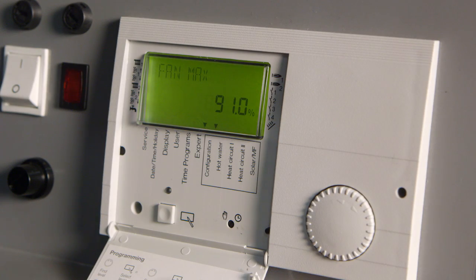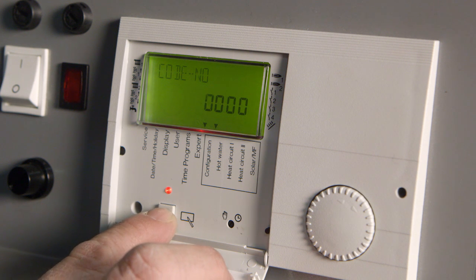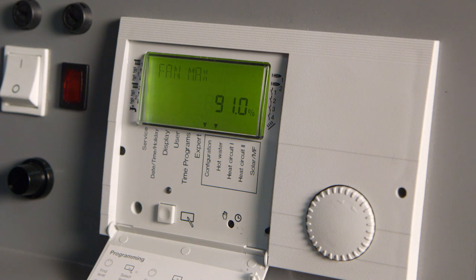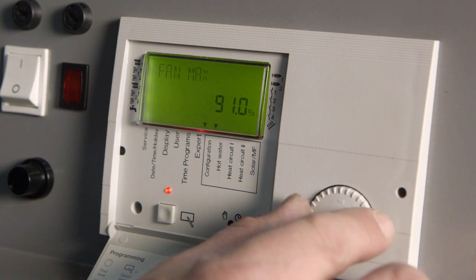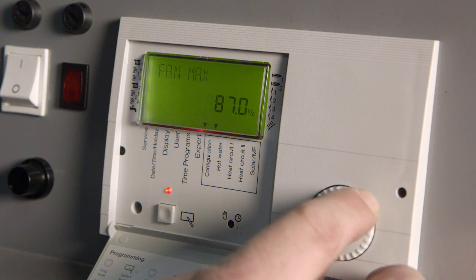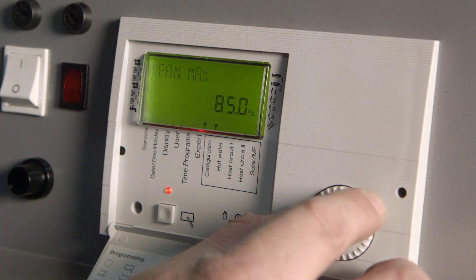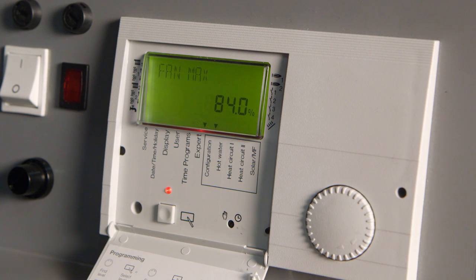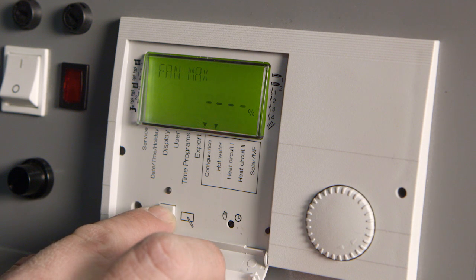Turn the wheel clockwise until max fan speed is displayed. Press the button to change this value, which requires a password. Press the program key 4 times to enter your code, and then a 5th time to continue. Hit the button again. The red light will glow. Now, use the scroll wheel to set your maximum fan speed to 84. Press the button again to enter this value.